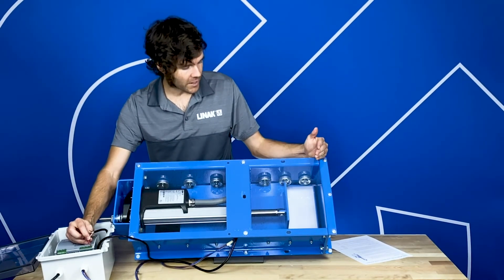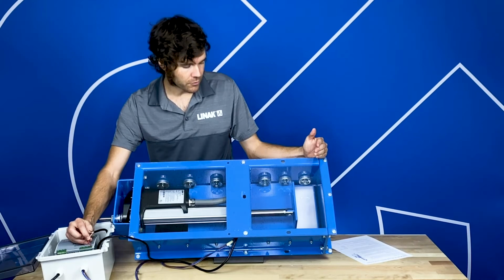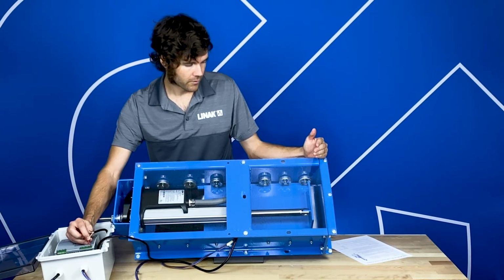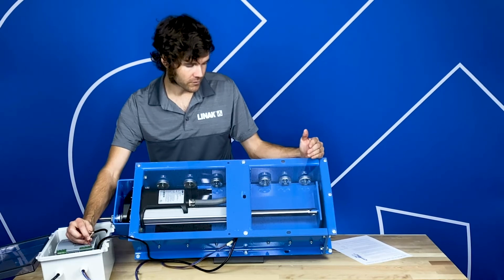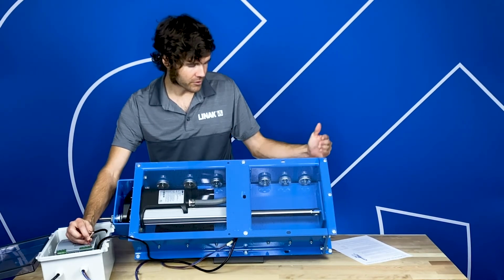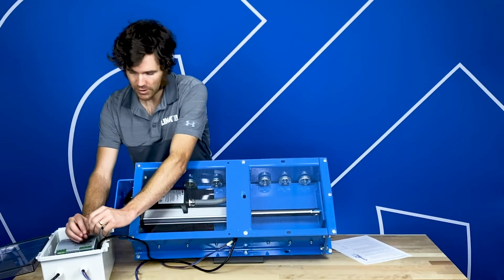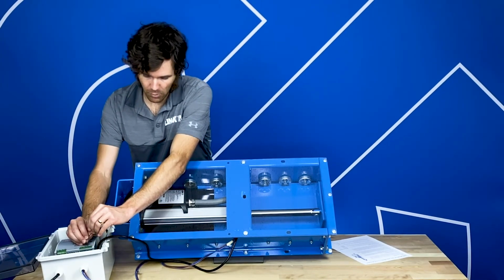Once it reaches the mechanical limit of the structure, it's going to go to a lower current cutoff, and then it's going to retract a few pulses to account for deformation of the structure. Okay, now the actuator has learned its position. So we're going to run it back in using the black wire.